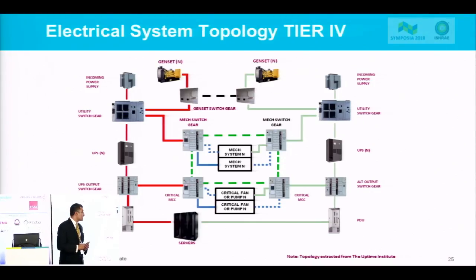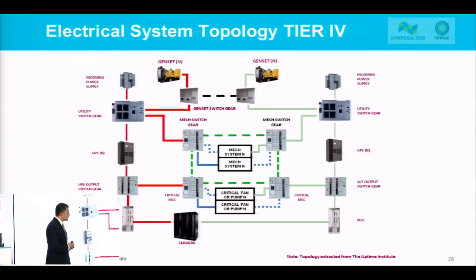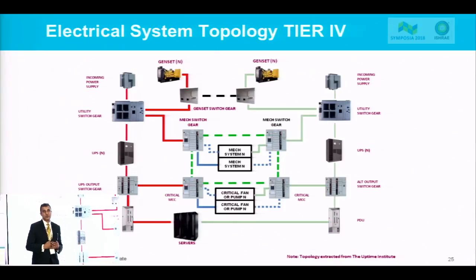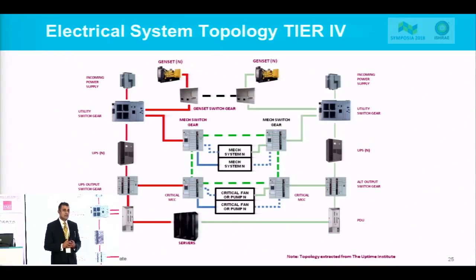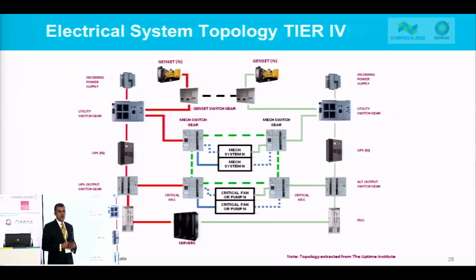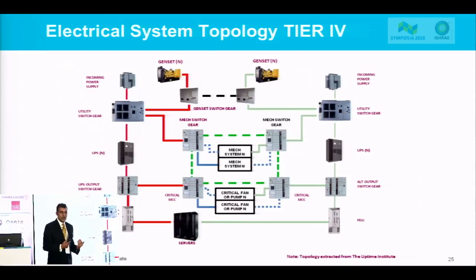So the tier 4 site is fault tolerant. It can take a first degree of failure. It has multiple UPS distribution. It's on a 2N topology. Each of the UPS system work at about 50%. Operationally, they go about 35 to 40% usually. Continuous cooling is required. Compartmentation is required.